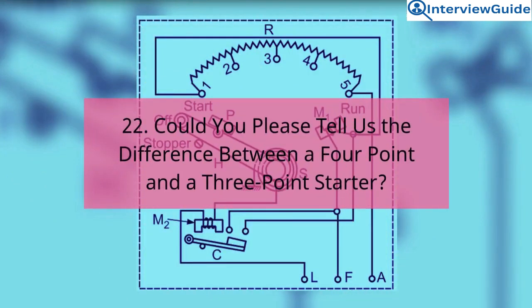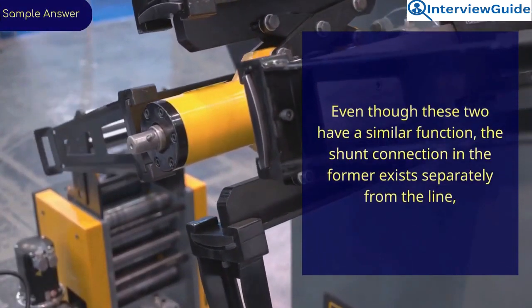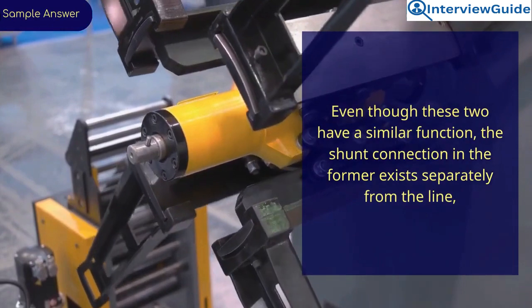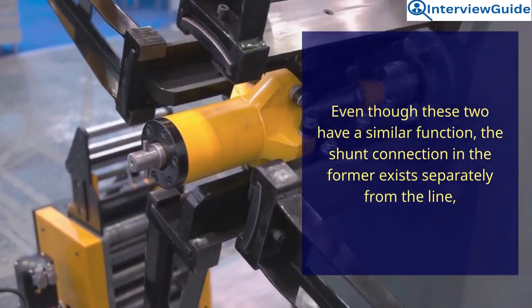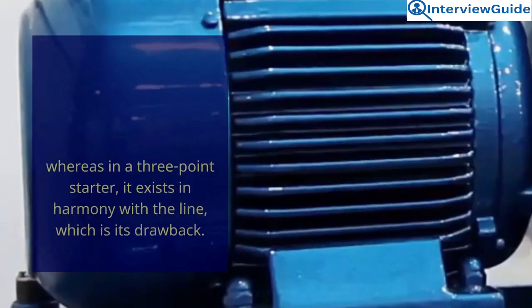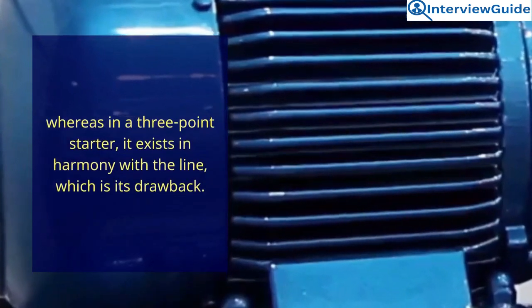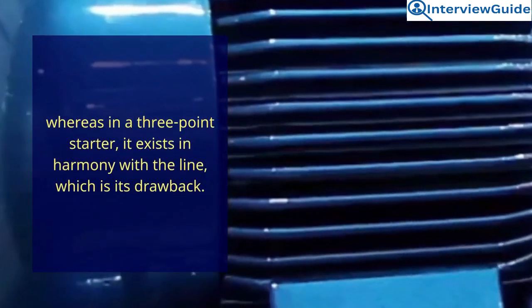22. Could you please tell us the difference between a 4-point and a 3-point starter? Sample answer. Even though these two have a similar function, the shunt connection in the former exists separately from the line, whereas in a 3-point starter, it exists in harmony with the line, which is its drawback.